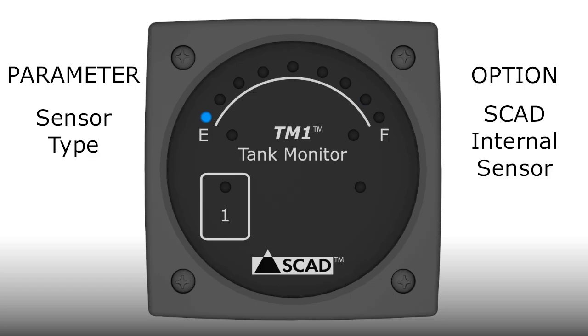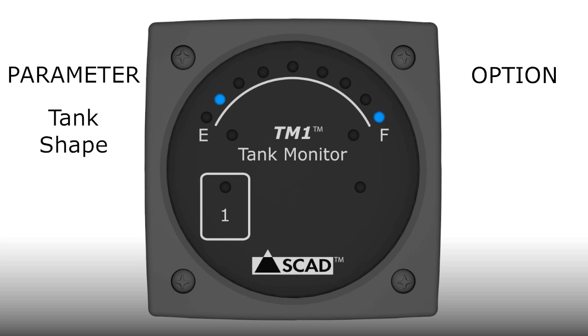Let's assume that's the option you want. To make the selection, just tap the touchpad and the light will go from flashing to constant, meaning it's selected. After 5 seconds on that option, the monitor will proceed to the next option, which is a 240 to 33 ohm float sensor indicated by the 3/4 light. Wait 5 seconds for the next option, which is the 10 to 180 ohm float sensor indicated by the 5/8 light. After this final option, the monitor will proceed to the next parameter, which is tank shape.